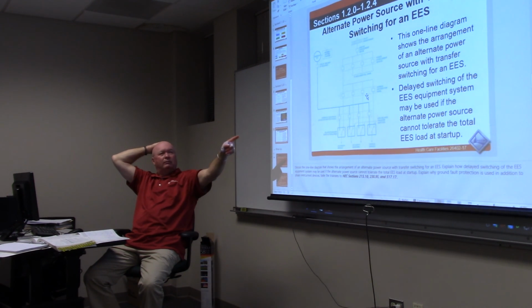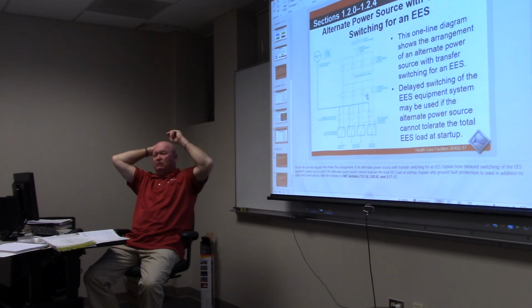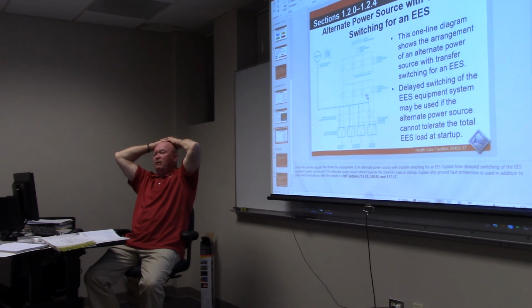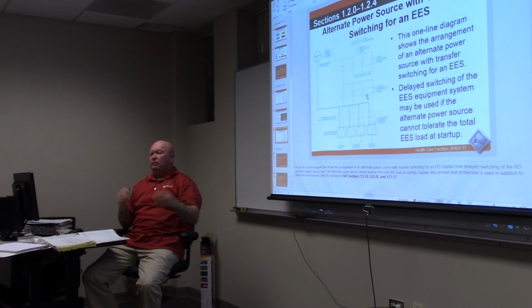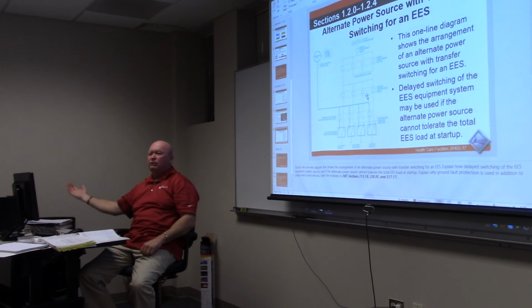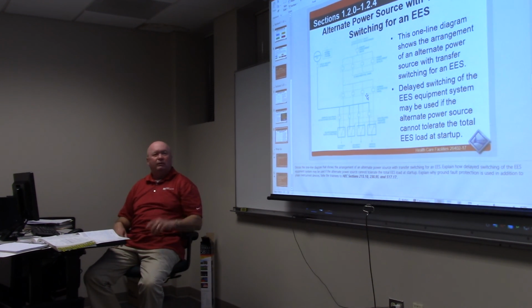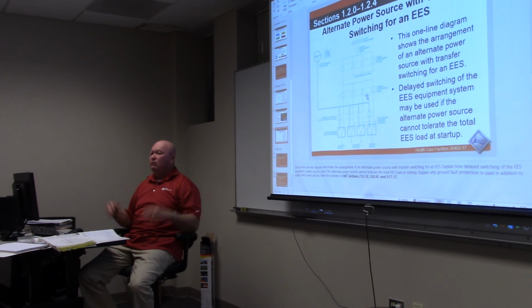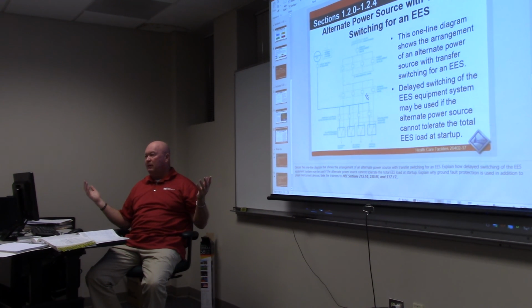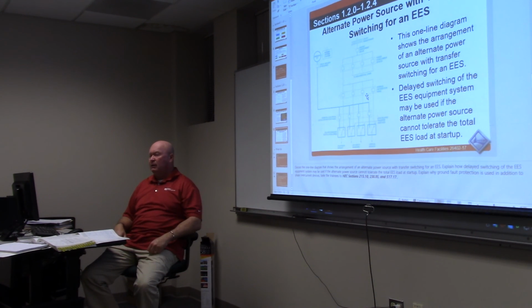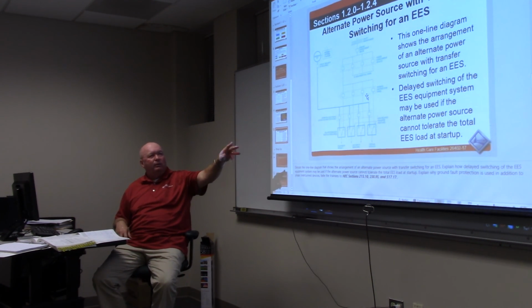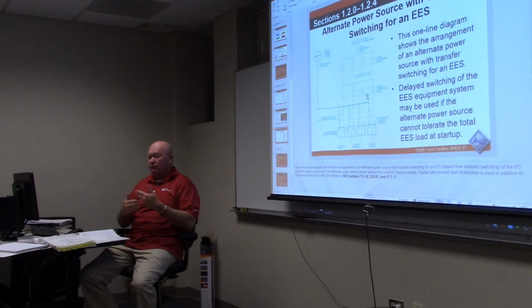Then what are we allowed to do? Delayed switching—coordination with the HVAC contractor so they put controls where Unit A comes on in 30 seconds and Unit B comes on in 3 minutes. The critical stuff comes up immediately, and you'd never know the air conditioning was off for those few minutes, especially if you're trying to get out of the building. That's probably where delayed switching is used the most—for HVAC units.